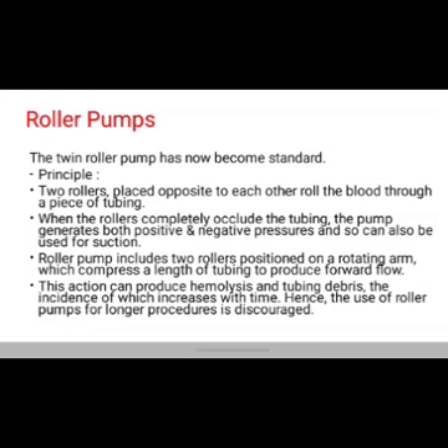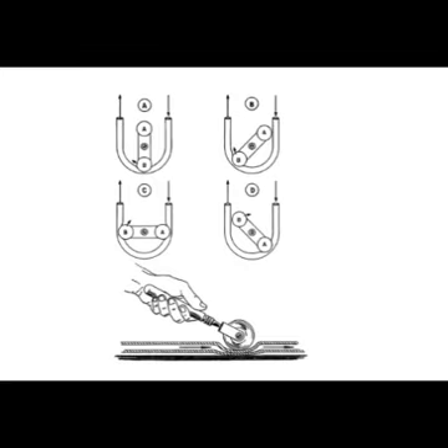It works on the principle that it has two rollers placed opposite to each other. Each rolls the blood through a piece of tubing. When the rollers completely occlude the tubing, the pump generates both positive and negative pressures and so can also be used for suction. The roller pump includes two rollers positioned on a rotating arm which compresses a length of tubing to produce forward flow. This action can produce hemolysis and tubing debris, the incidence of which increases with time. Hence, the use of roller pumps for longer procedures is discouraged.